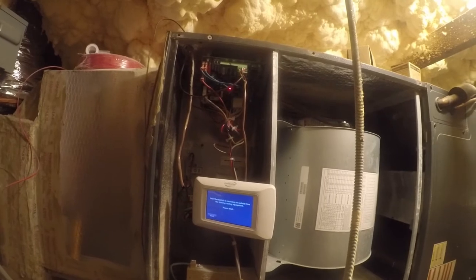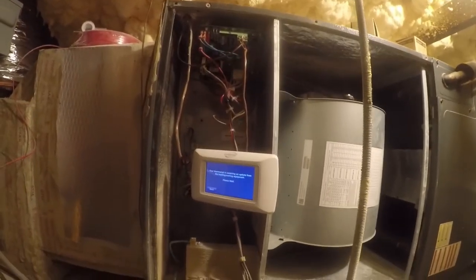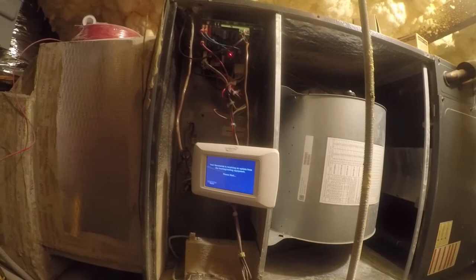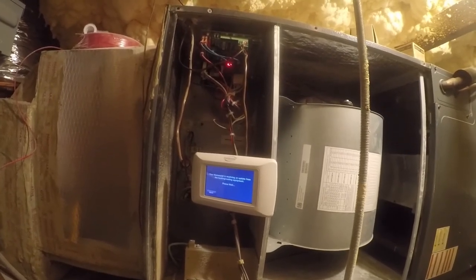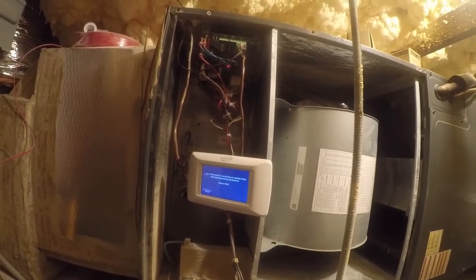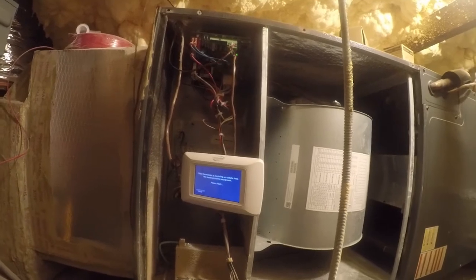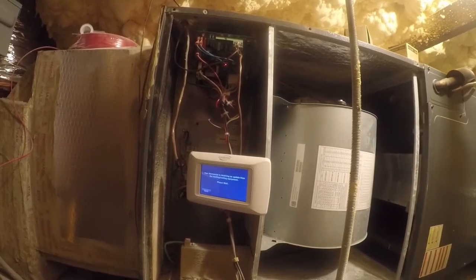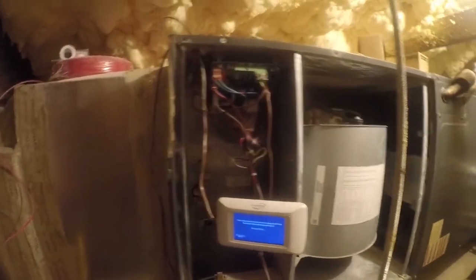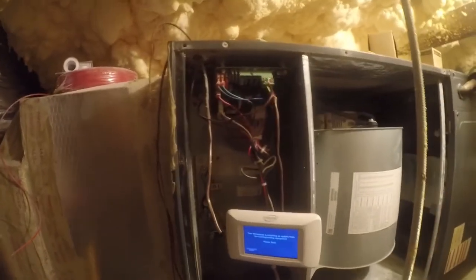I've been happy with the thermostat, but it's discontinued and stupid expensive — and by the way, I'm going to have one for sale if you want to pay me 300 bucks for it. This was installed properly and has been running perfectly for four years, at least as perfectly as a Goodman or Amana unit can run, up until the nearby lightning strike last night. So back to where we're at: I think we've got a dead ComfortNet communications bus, and I actually think the failure is here because it cannot find the blower unit when it's connected to the blower unit and there's nothing else there — that's a pretty good indicator that this side of the communications bus is dead.